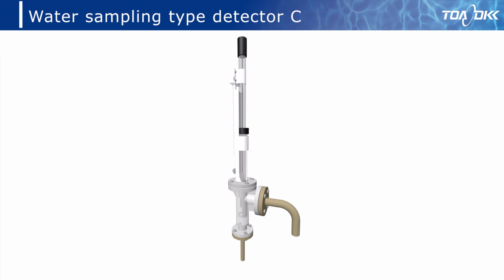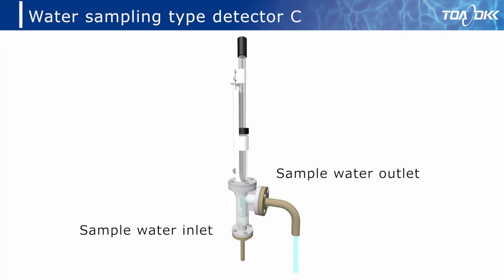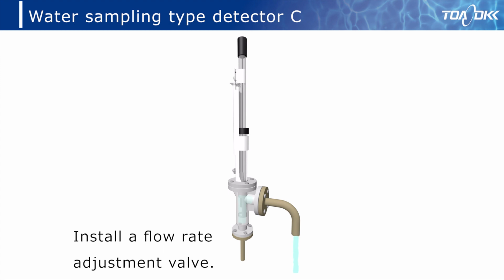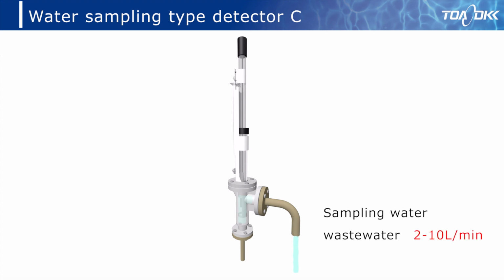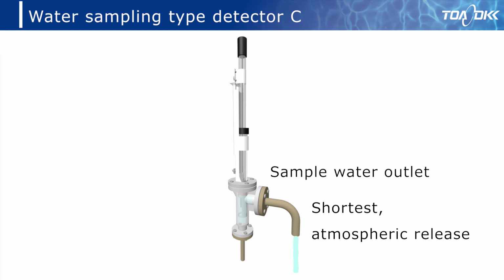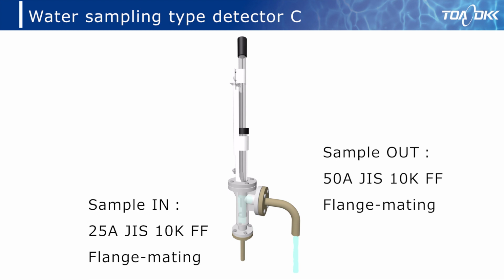The third specification is the water sampling type detector. Its case, the chamber, is attached to the piping. Measure the sample water under pressure by flowing it. The bottom is the sample water inlet and the side is the sample water outlet. The yellow part is the customer's piping. Install a flow adjustment valve in front of the sample water inlet. Sample water flow should be within the limits of 2 to 10 liters per minute. The sample water drainage should be as short as possible, and open to the atmosphere so that back pressure is not applied. Standard flange specifications are as follows respectively.